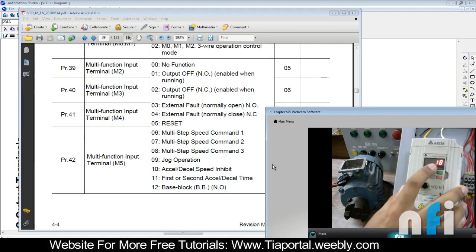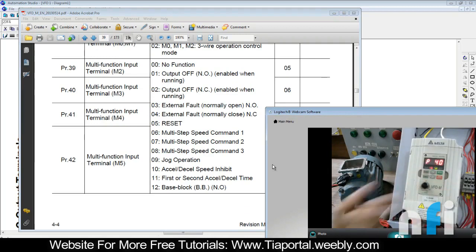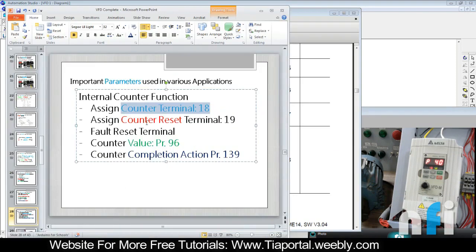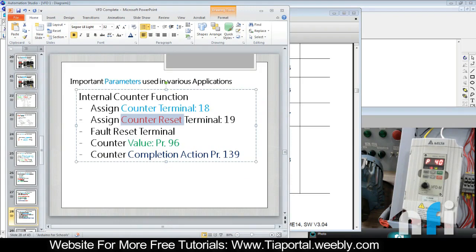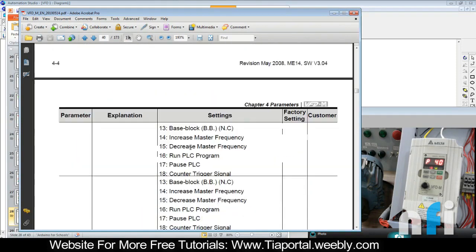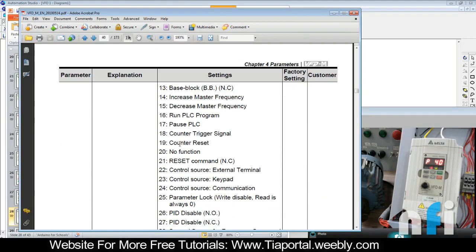When it starts counting, it needs a counter reset terminal as well, which can be used to reset the counter in case needed. The next terminal we have taken is counter reset. So M4, parameter 41, we have entered counter reset. In parameter 41, we have 19 already there, so it will reset the counter.